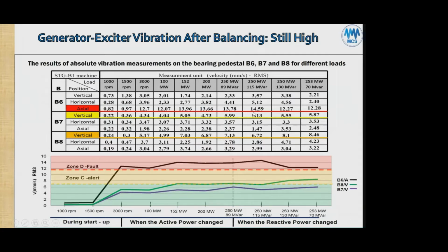So if you recall in the previous slide, I said if you're going to balance generators and rotors, steam turbine rotors and gas turbine rotors, you must operate them preferably at a no load condition first, get full readings at that point, then go to a half load if you can, and then go to a full load. You want all of these: zero load, half load and full load. Don't jump from zero to full load, because you're going to get insufficient data. You want all three.